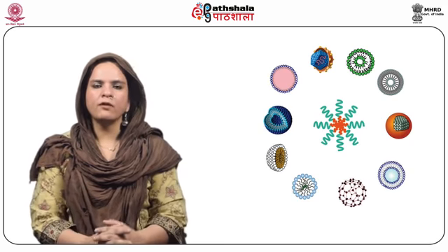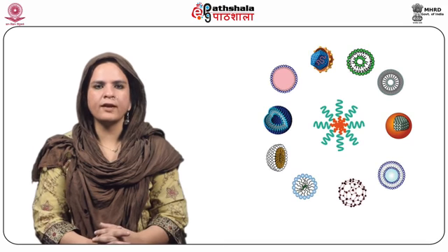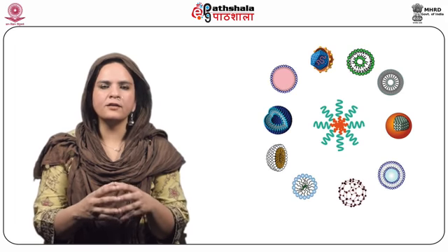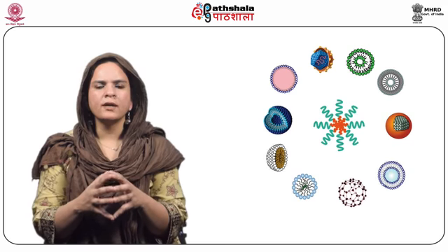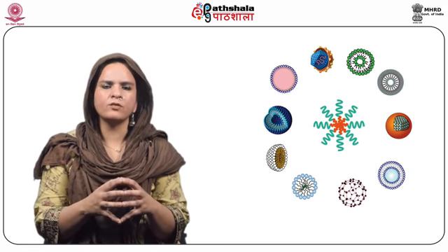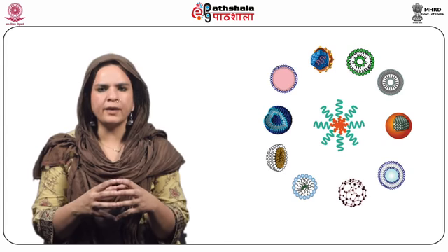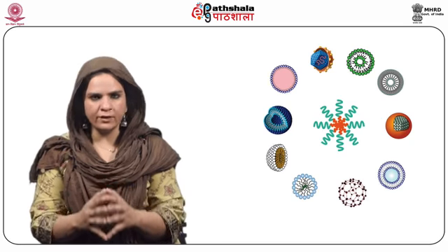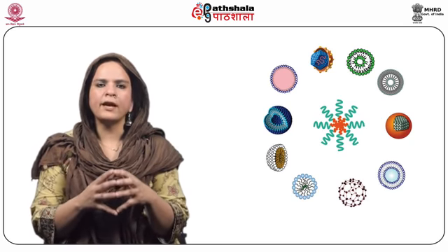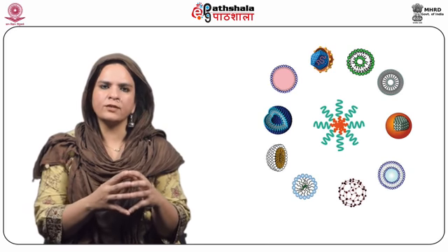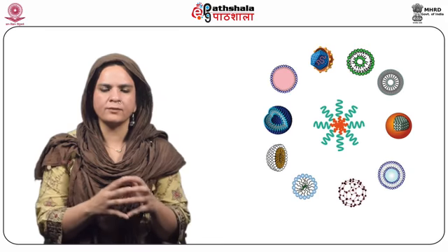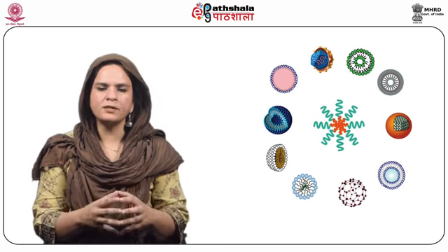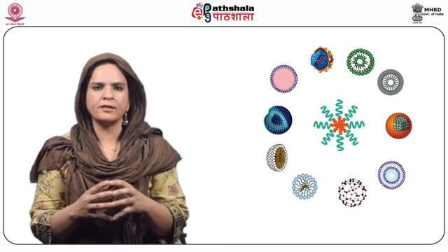Towards the end of this module, we also tried to emphasize the various recent innovations in sterile drug delivery devices. We had the needle-free device. We talked about the latest technology wherein we had a pen which was also supported by a memory, which simply implies that whenever that drug delivery device is being used, it will not only deliver the drug at that point of time, but it will also keep a record of how much was delivered at what dates and what times. This would come handy in giving the best possible care to a person who is suffering from chronic diseases like diabetes mellitus.